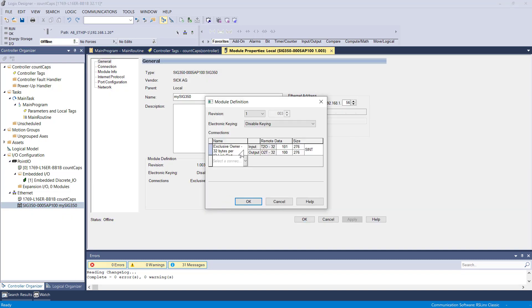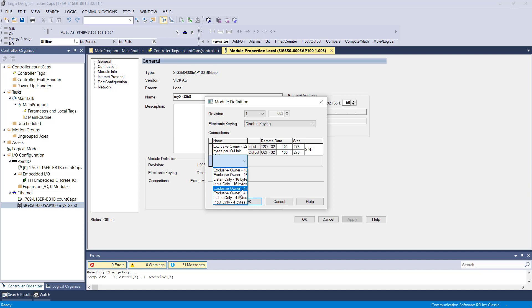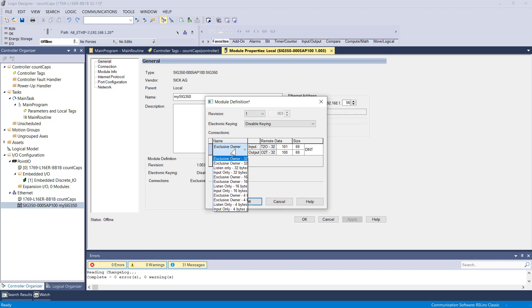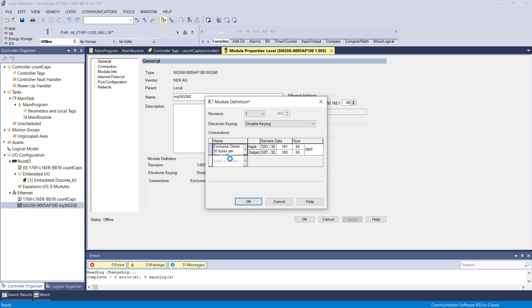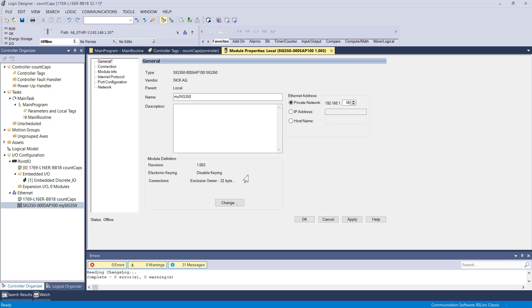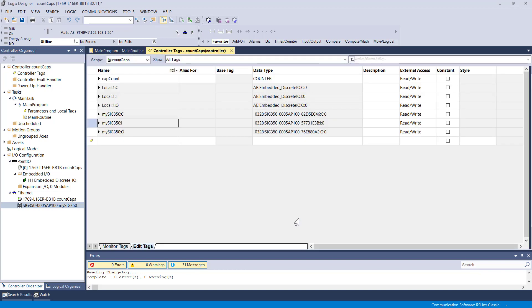Regarding the settings for the module that I configured here, I can see that we've got a SINT. So that should be changed to DINT. And then I'm going to keep my exclusive owner 32 for the connection configuration. And then just click OK. Want to change it? Yes.